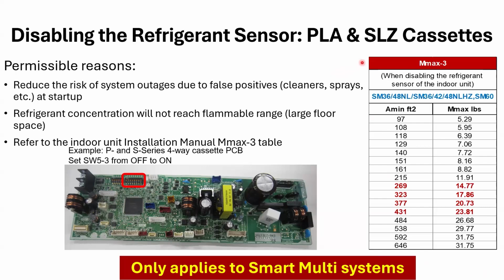So probably just easier to go across the board and say, all right, we're just going to leave them all active. So when disabling the refrigerant sensor of the indoor unit, again, right here, talking about the minimum square foot area where that system's installed. Like I was saying, this is kind of the sweet spot where we're going to be. I would say maybe a little bit more down here to 26, 29.